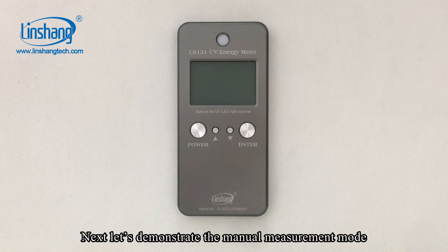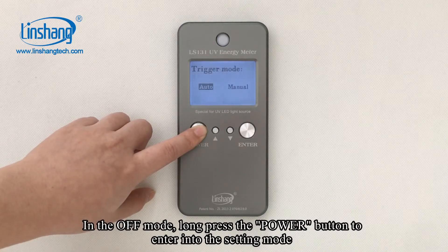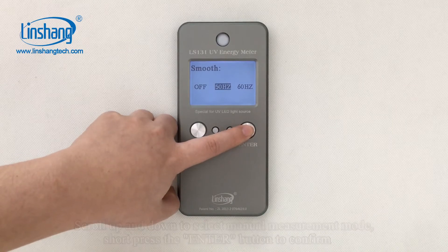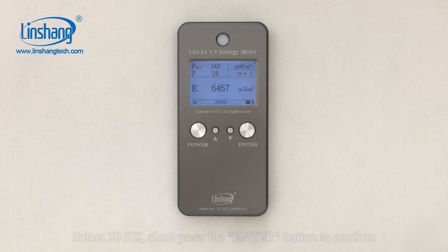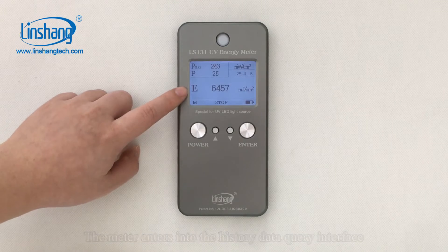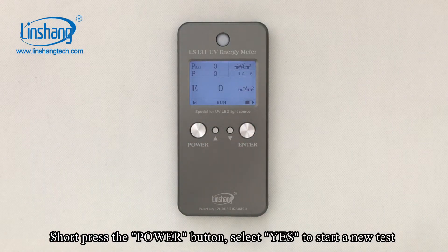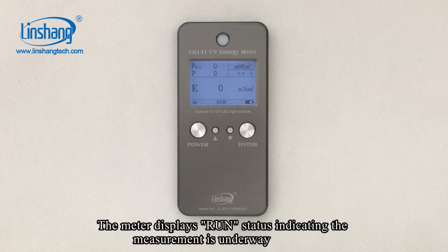Next, let's demonstrate the manual measurement mode. In the OFF mode, long press the Power button to enter into the setting mode. Scroll up and down to select manual measurement mode, then short press the ENTER button to confirm. Select 50Hz and short press the ENTER button to confirm. The meter enters into the history data query interface. The data you see now is the data measured last time. Short press the Power button and select YES to start a new test. The meter displays the running state, indicating the measurement is underway.